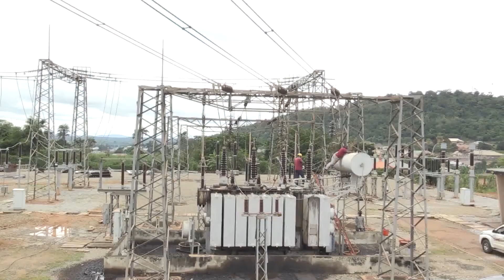At the Kubwa substation, TCN said one of the 60 MVA power transformers, which developed a fault, was taken out for repairs, and a replacement has been procured and will be delivered soon. However, the second transformer in the substation is transmitting a full load of 42 megawatts, which can adequately take care of the load requirement for the Kubwa axis and environs.